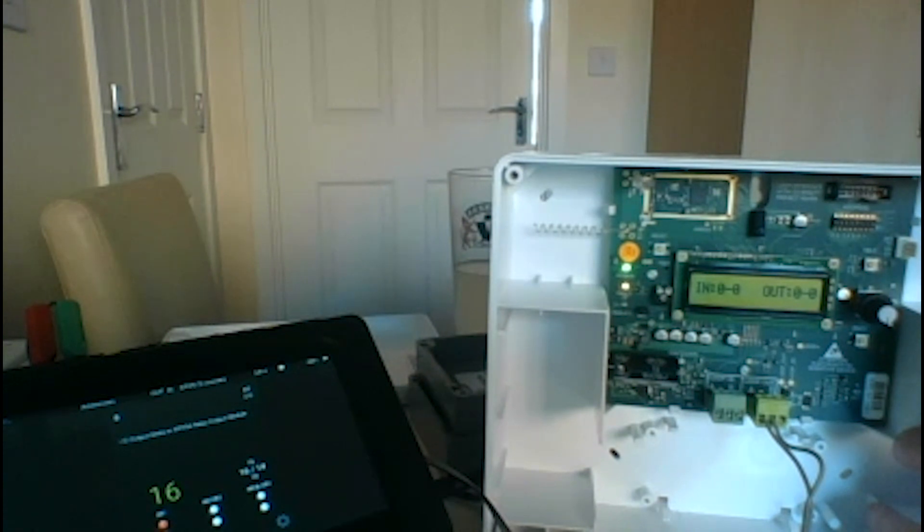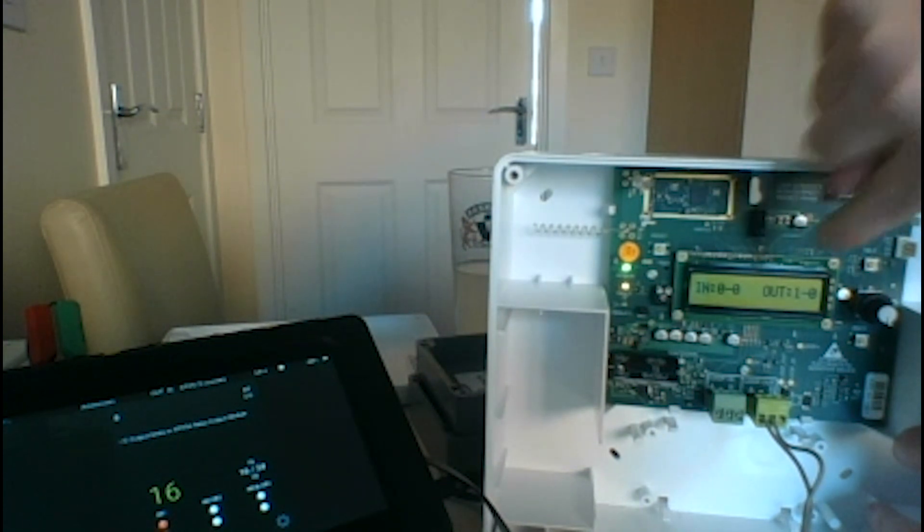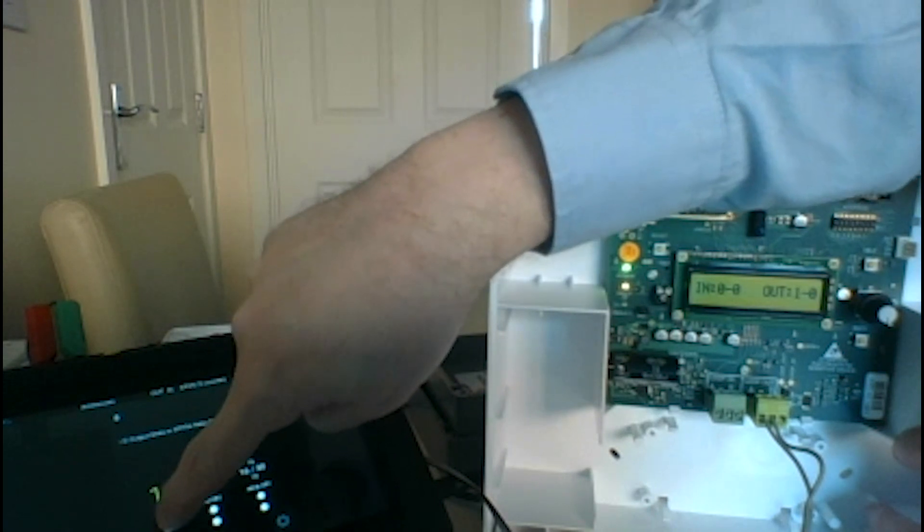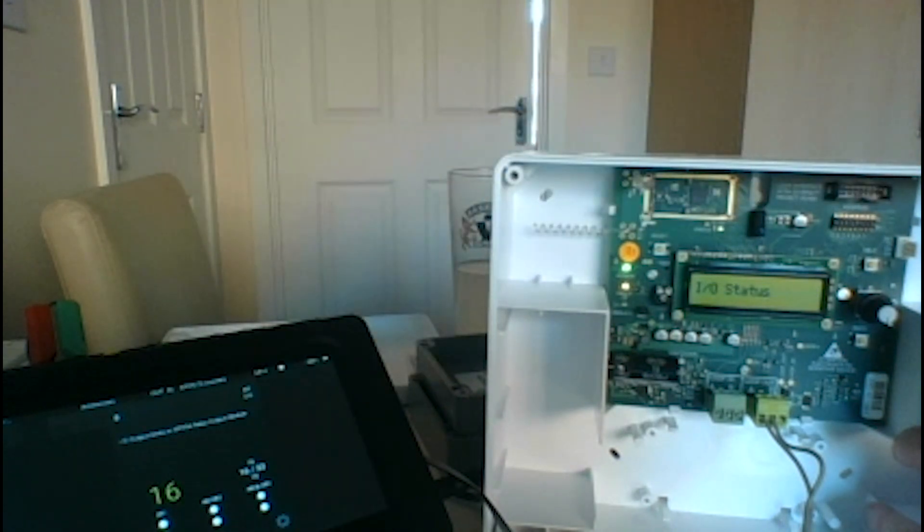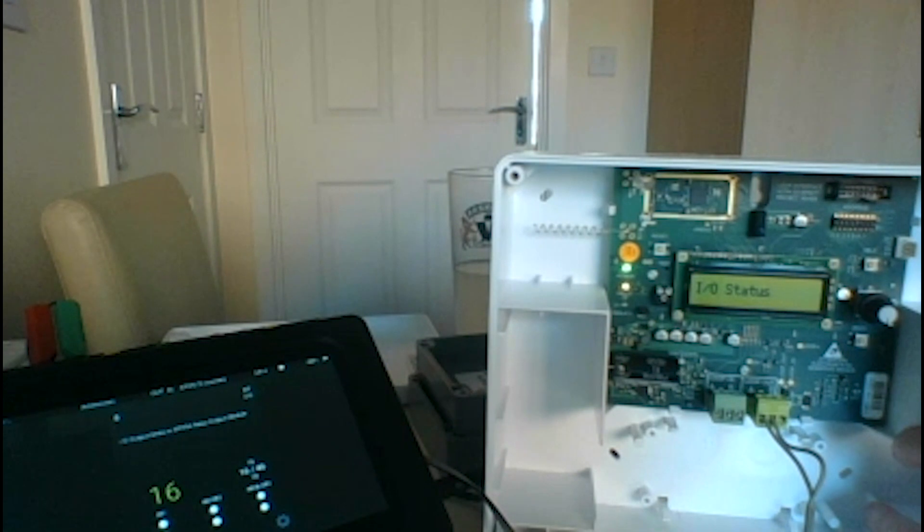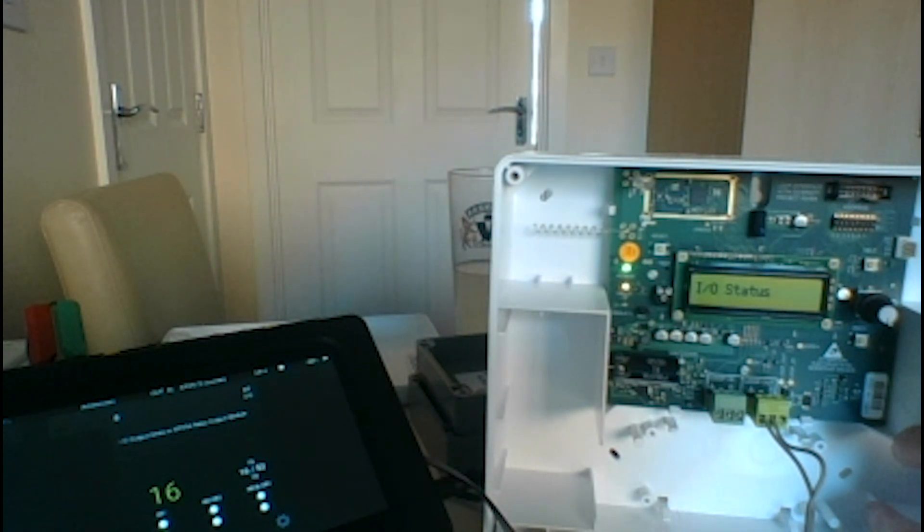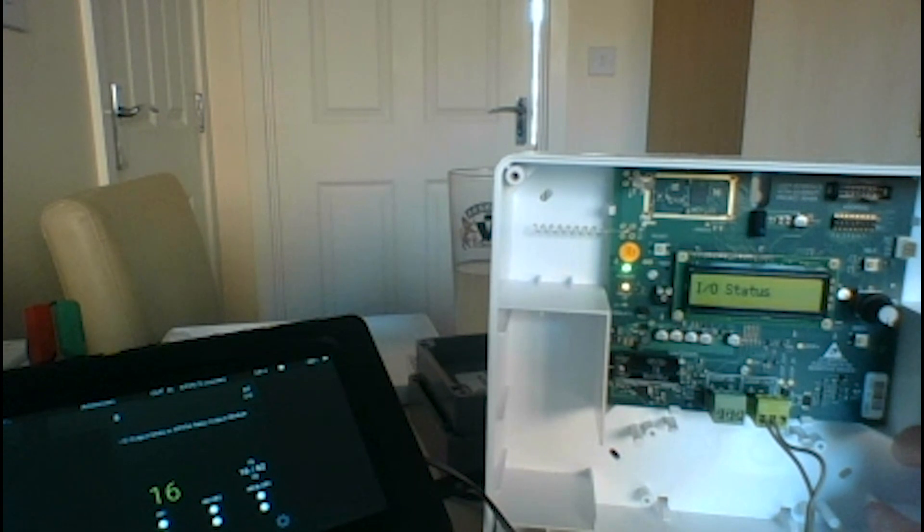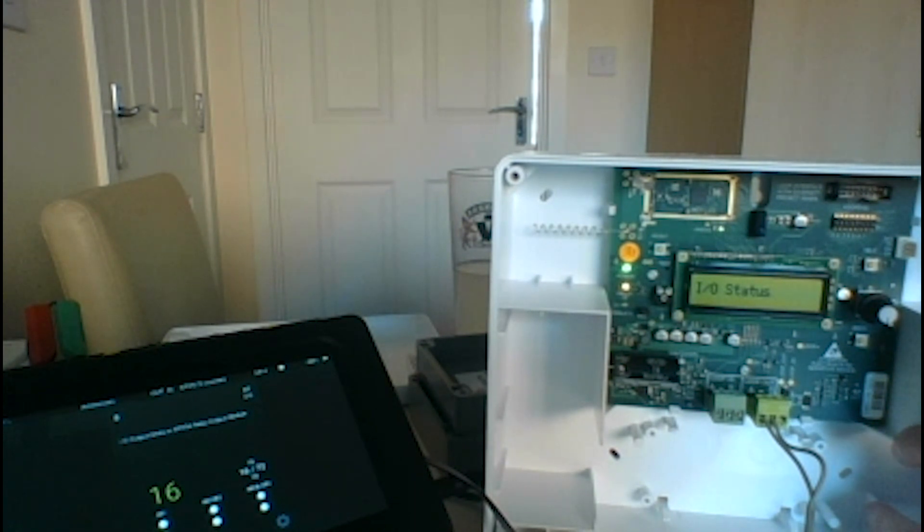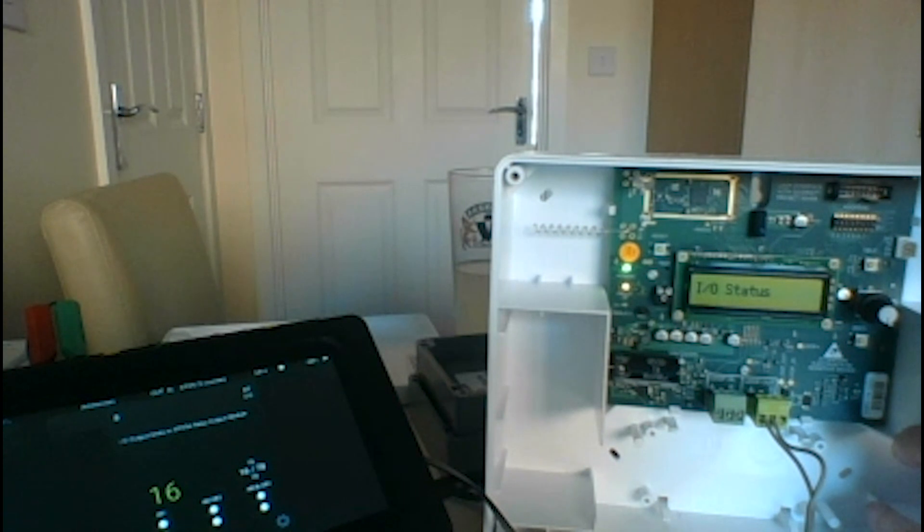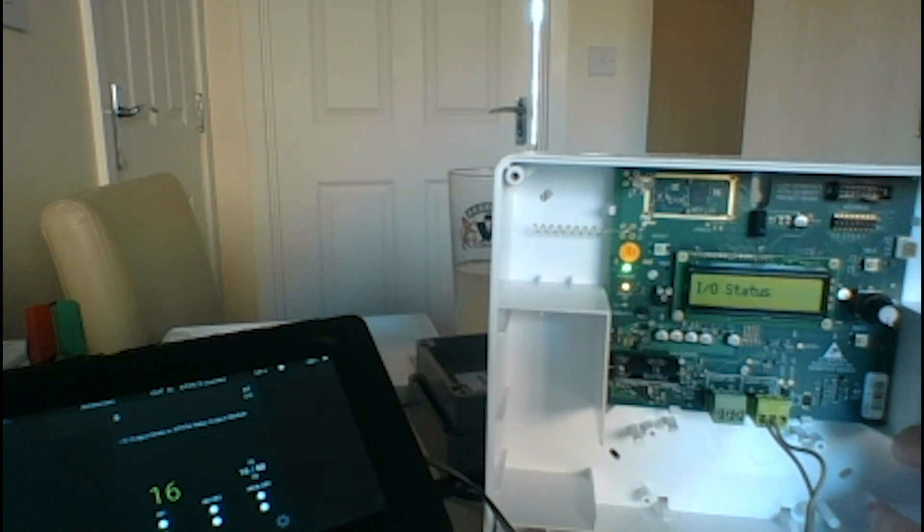When we send the output command to the unit, it changes the output bit. Now as with all input output units, the control panel is monitoring the input side and operating the output side, so they're two separate things - they're not connected. An input comes in, the control panel can act on that.